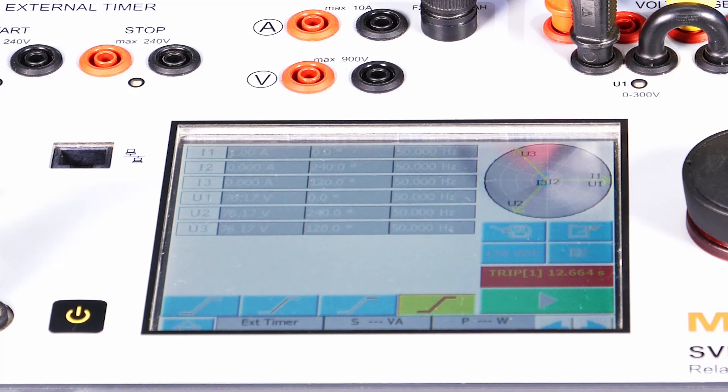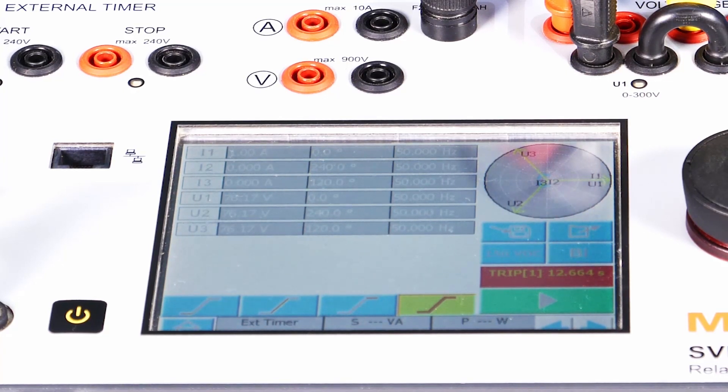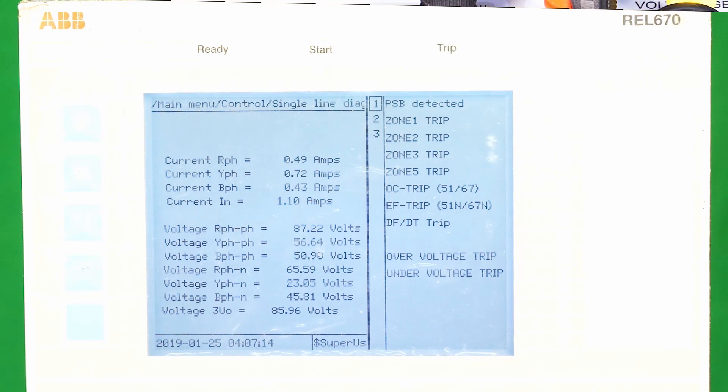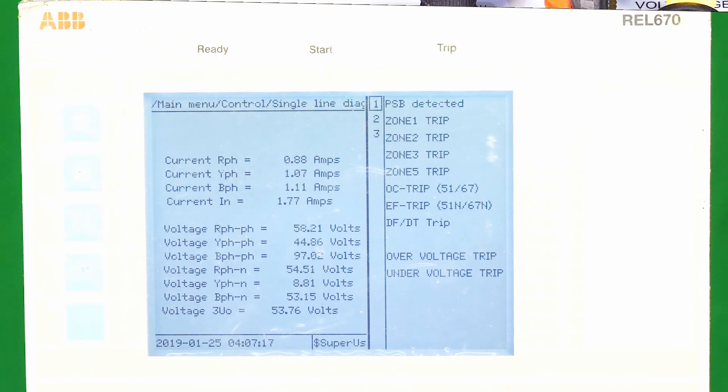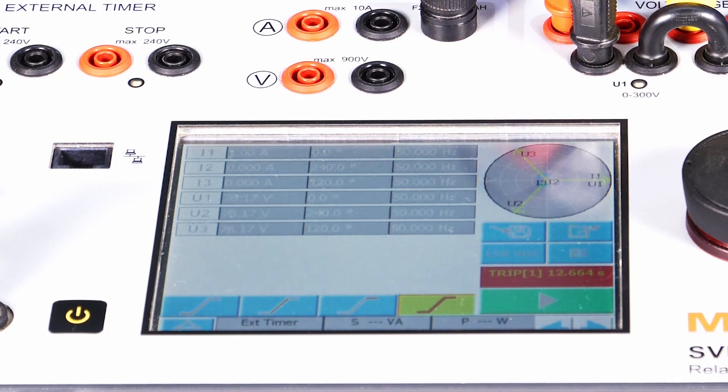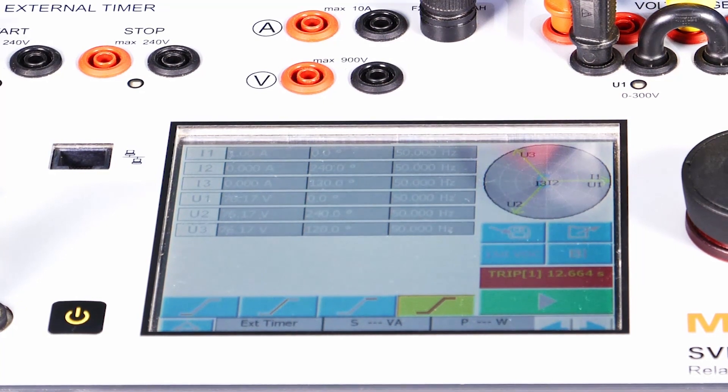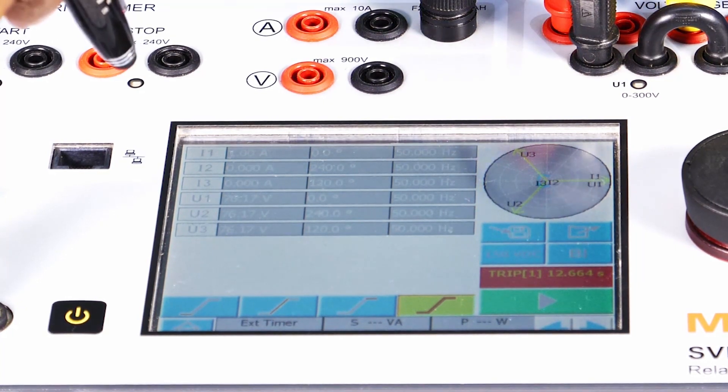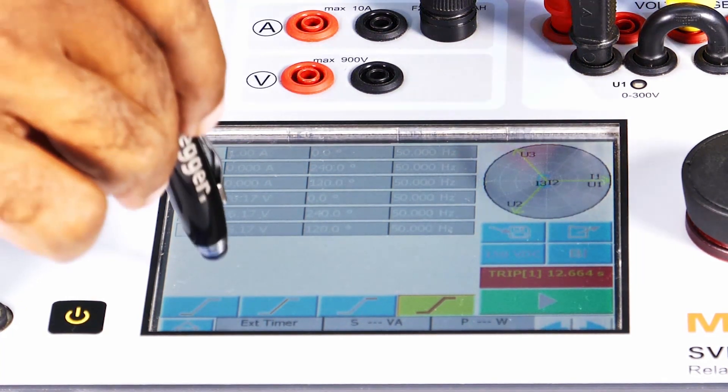Ramping over voltage application example. An ABB make REL 670 relay is configured for 120% as over voltage settings with 0 millisecond time delay to test this feature in the ramping screen.